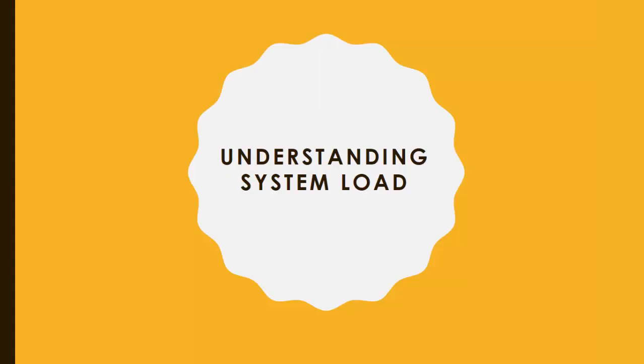Understanding system loads. Your client will say, I want AC, I want freezer, I want washing machine to be on the solar system. You have to lecture them. These loads are inductive in nature. They have high starting current and they are getting this current from your battery. The battery is the heart of the solar system. So if you drain your battery more than enough, the system will collapse soon.